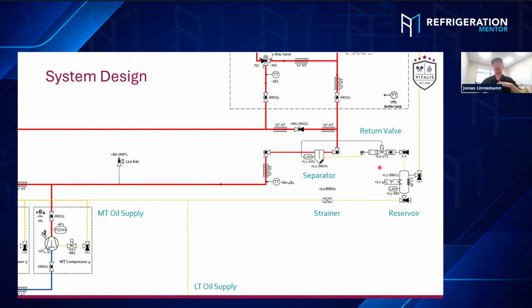We do have a little tiny self-made block here, which also includes a strainer upstream and a little sight glass downstream, because we just talked about how it's nice to look inside at what's really coming back and see the oil quality. As soon as we drop the high-pressure oil down into the oil reservoir, where it's stored to get supplied to the compressors, we have basically the same effect we talked about earlier. The lower pressure is degassing the CO₂ out of the oil, so we already reduce the CO₂ amount inside the oil to have as pure oil as possible.